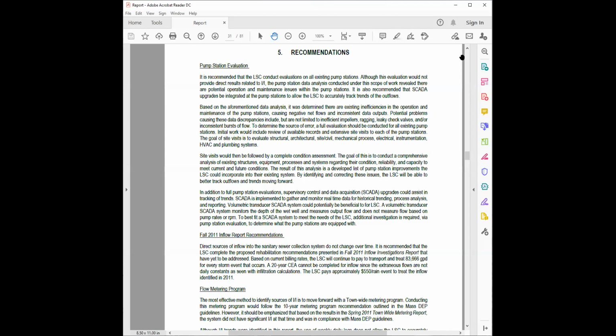The lack of SCADA in your system and the reliance on pump station resolution has really been around the question of what's the pump doing, what is the outflow. Flow metering is nonexistent for the most part in those pump stations, so it's a mathematical process. SCADA would make a significant improvement to your ability to trend data, to see the deterioration or functionality of the pumps, the wear on the pumps, and the operational efficiencies or lack thereof.